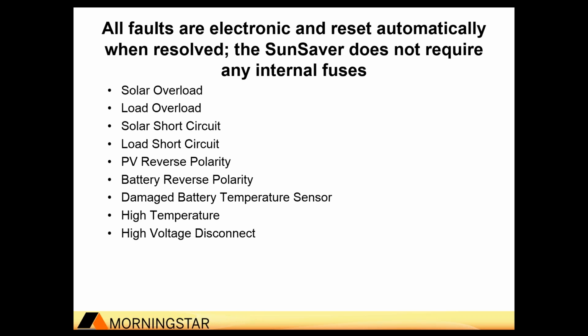The most common failure mode for most solar systems in remote areas is always going to be lightning, and so we always recommend system level lightning protection. But within our control, something that still sometimes occurs is an over voltage on the input. For the 12-volt Sunsaver models, it can only accept 30 volts. For the 24-volt models, the limit goes up to 60. So if you wire a few panels in series versus parallel by mistake, you could run into some problems. But in general, if you follow commonly used design procedures, you shouldn't have an issue.